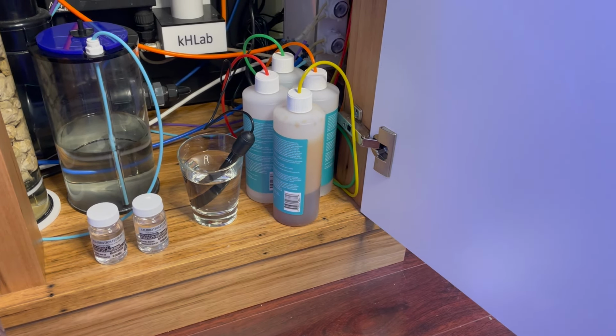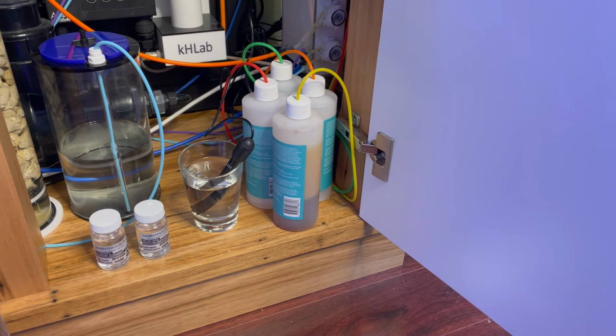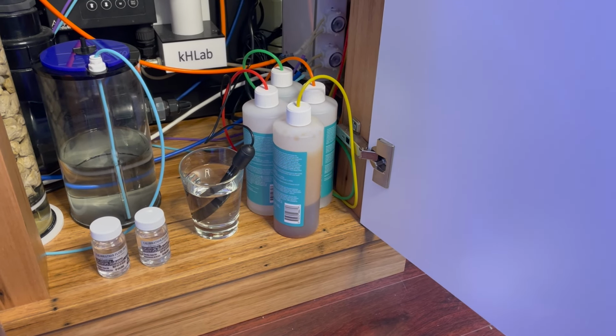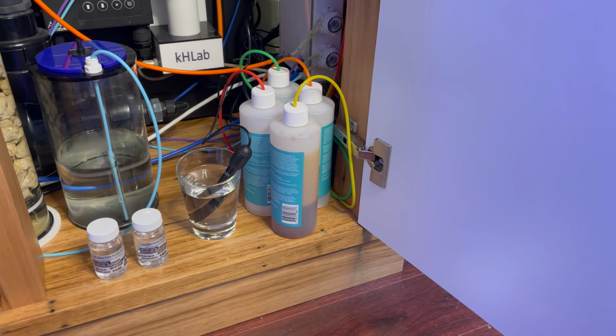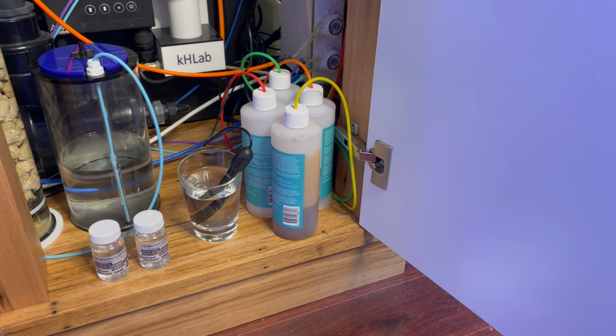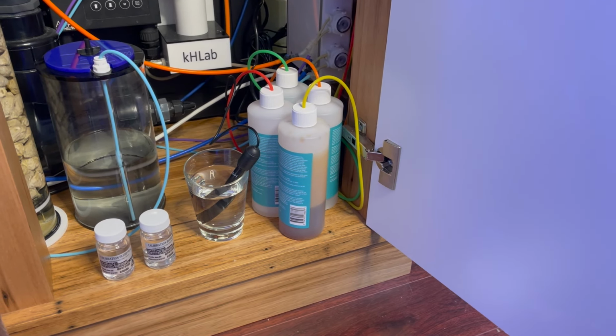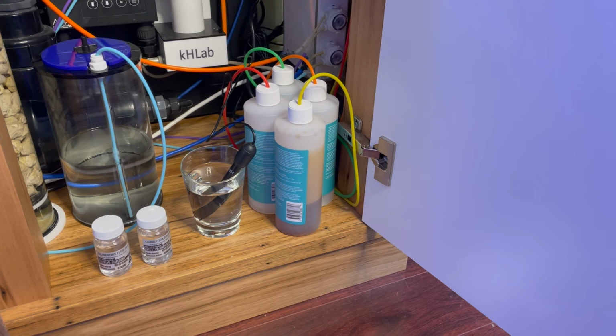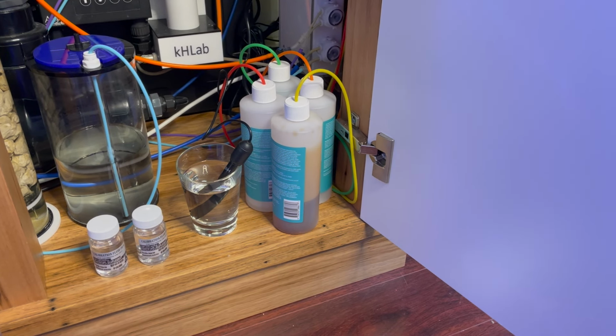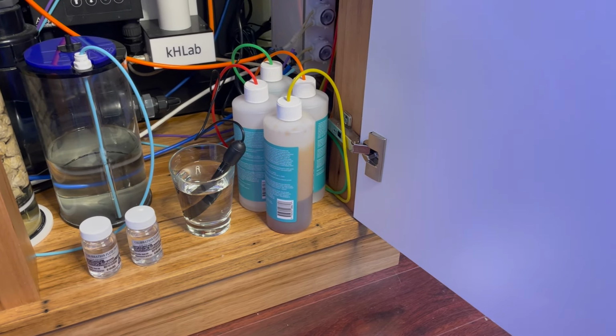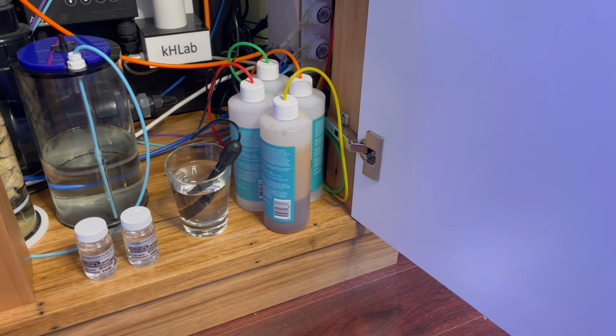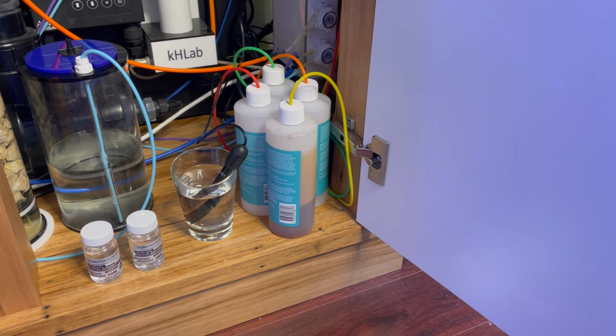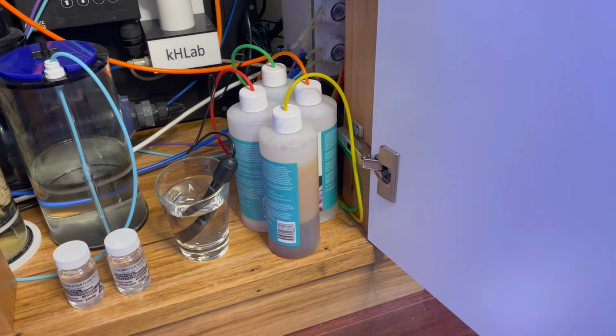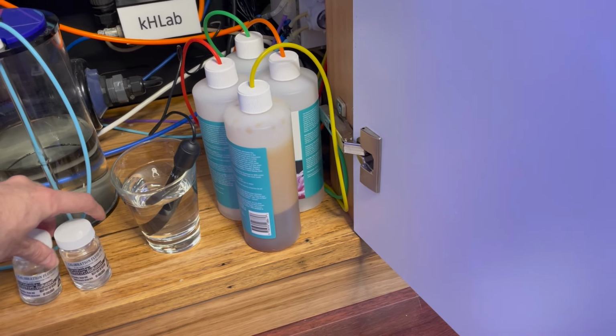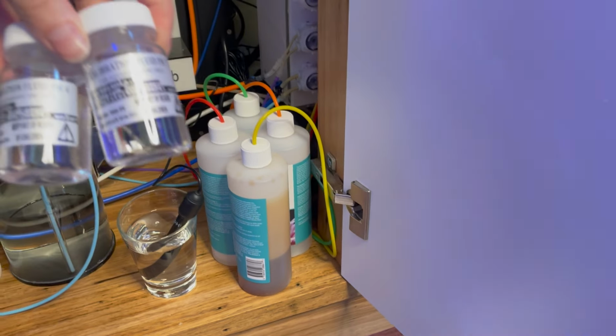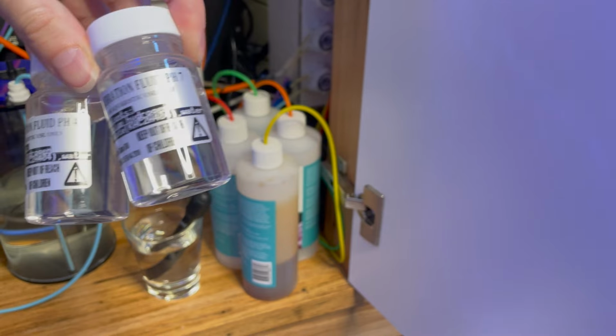Sometimes they get a little bit dry in shipping, or the little bottle that's often included on the bottom of them can be dislodged and some of that liquid can seep out. So you just might need to rehydrate the probe a little bit. You also want to wash off that potassium solution that they've been soaking in. So just soaking it in RO for 20 minutes before starting is good practice. You're also going to need the 2 calibration fluids that come with the KHLab. There's calibration fluid pH 4 and pH 7.